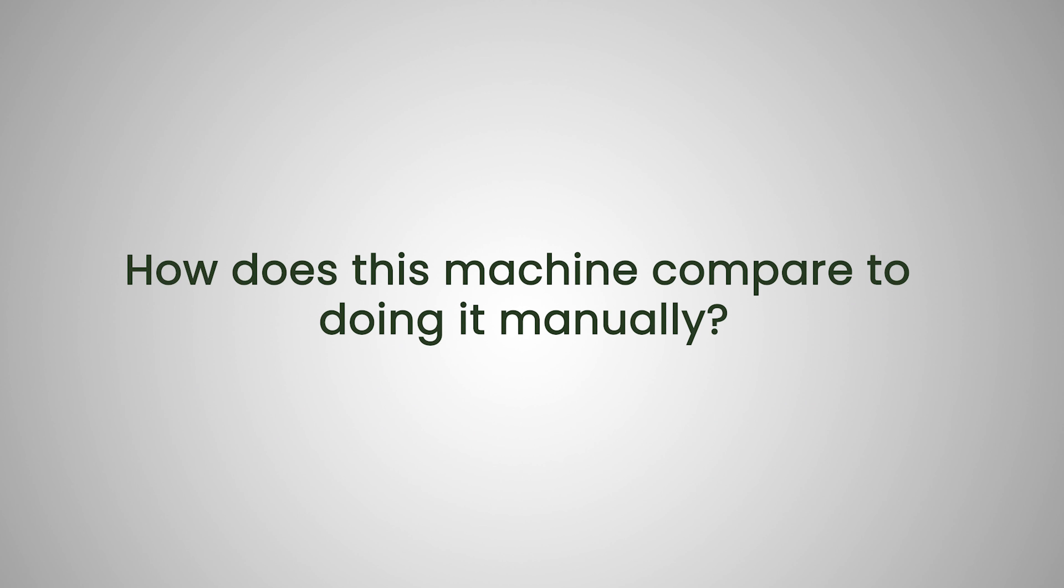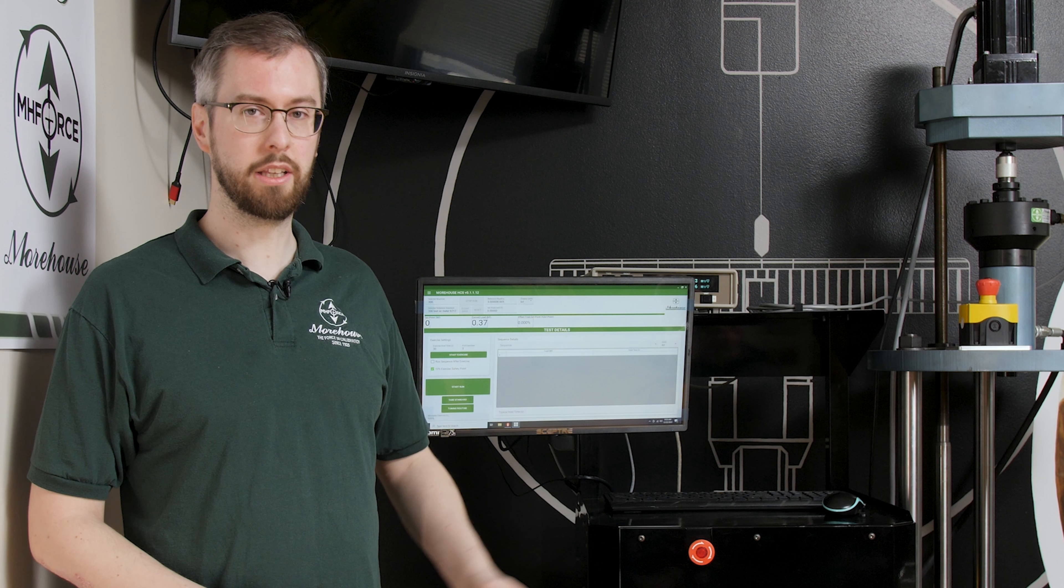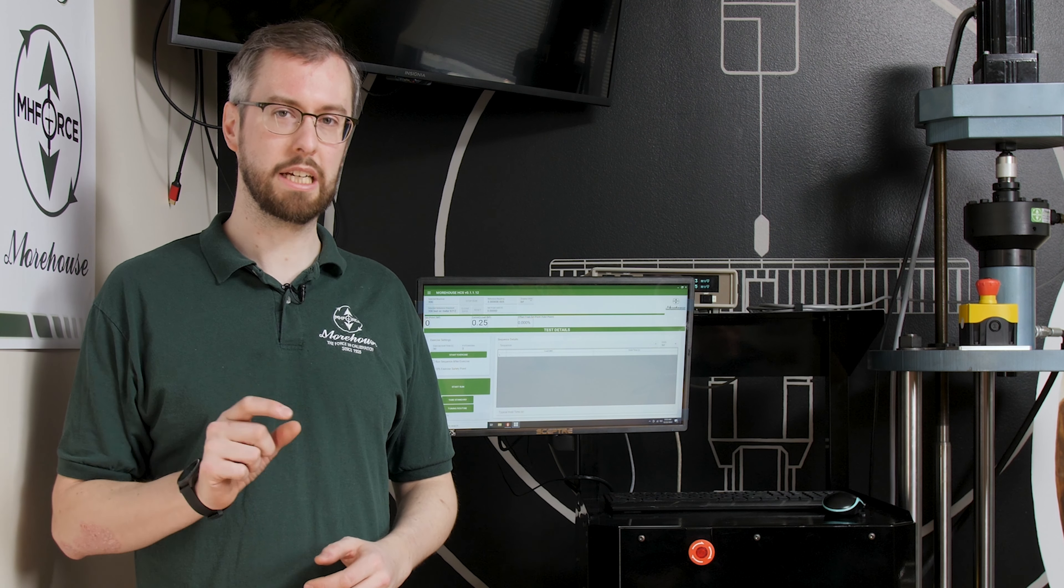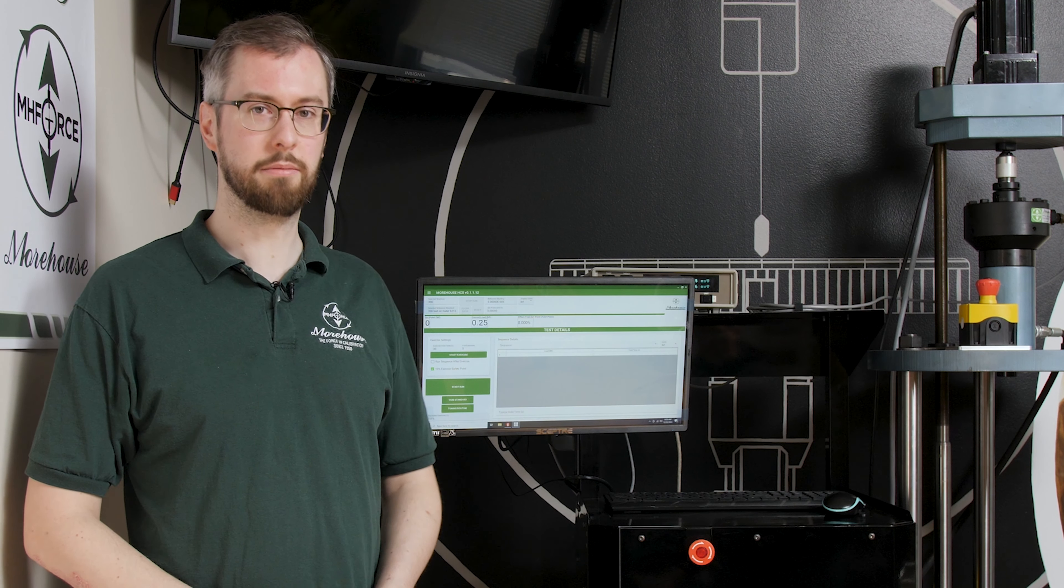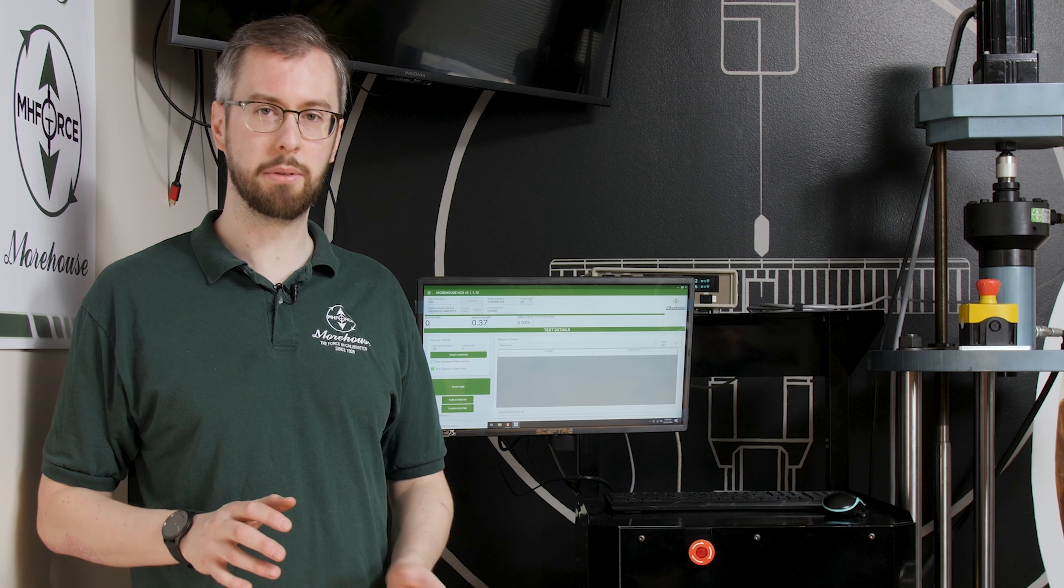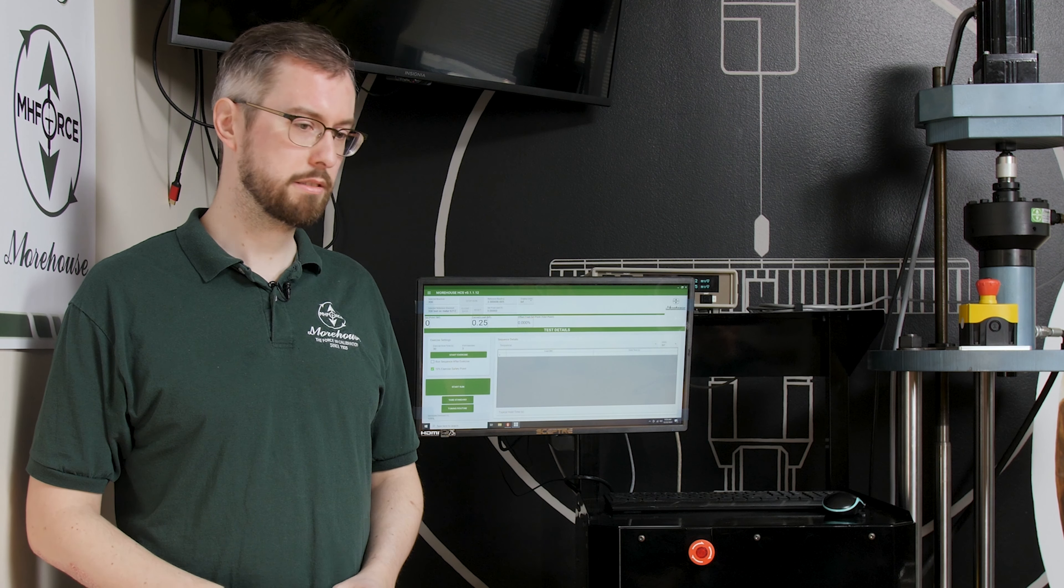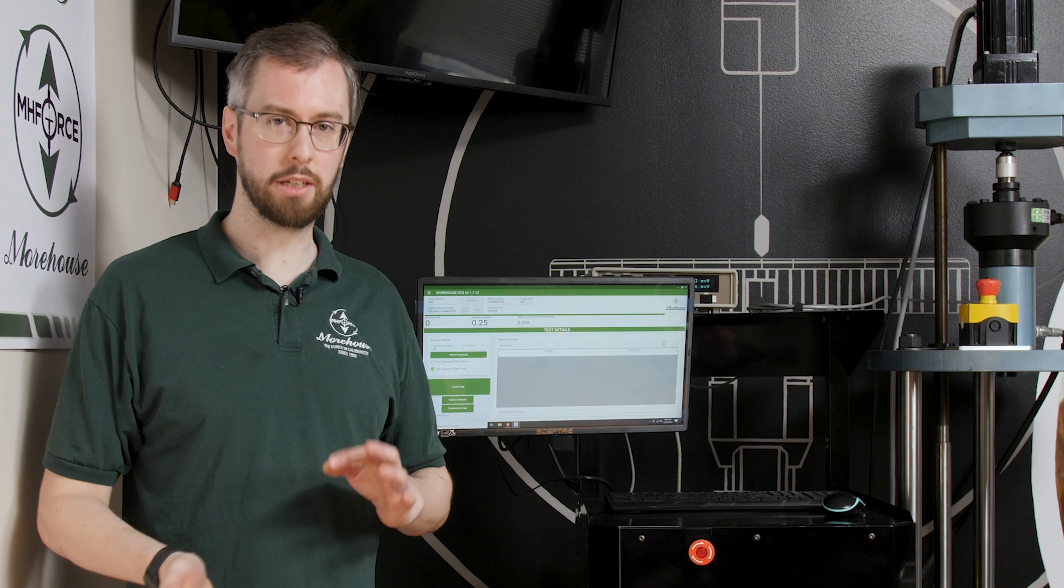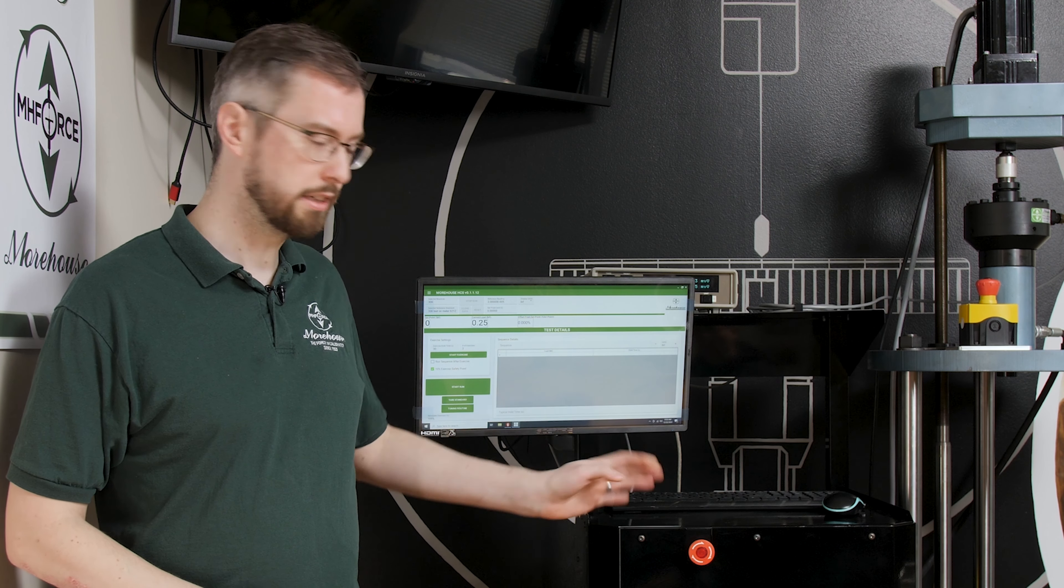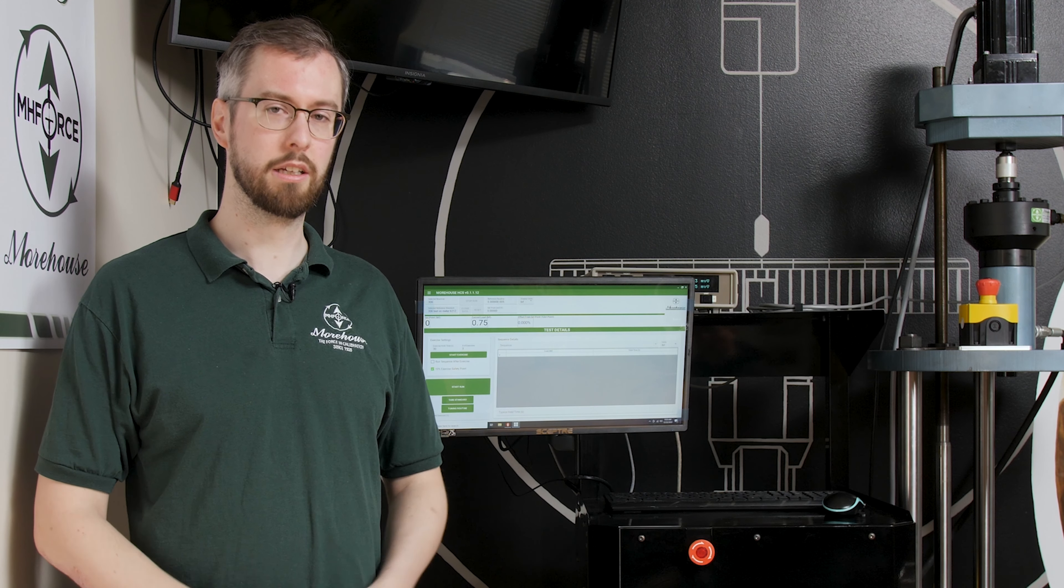How does this machine compare to doing it manually? So, I don't know if you ever try to control one of these machines manually, but it can be tough to hold a point within a really tight tolerance. The automated system can hold a tighter tolerance than a person can generally do, so you get better repeatability, and even, you get some variability between technicians. This is going to do it the same every time, so you get better reproducibility between cals.